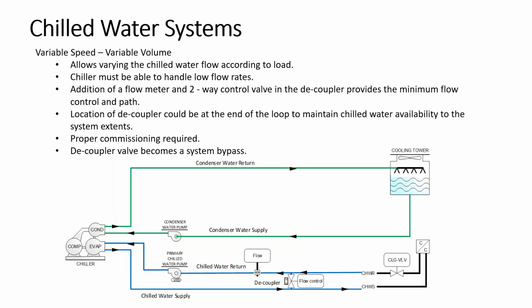Nowadays, with the advent of variable speed drives, we put variable speed on chillers, pumps, and everything, so that we can maintain the flow through the system by the use of a decoupler. This way we can pump water, and if you notice, these are primary only so far. We only have the one chilled water pump. We put a variable speed drive on it, we vary the flow through the system, but what happens is we can actually control the low flow by a bypass valve through a decoupler pipe that allows me to bypass the flow to maintain the minimum flow for the chiller and keep it online.